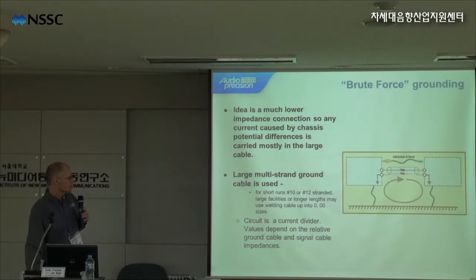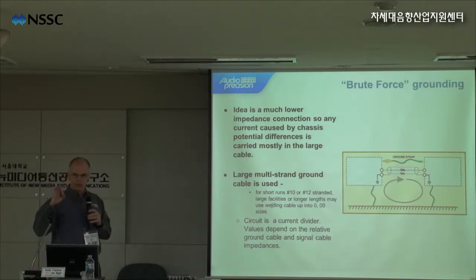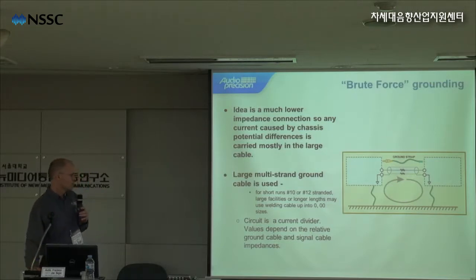So it's a multi-strand ground cable with, for short runs, it can be number 10 or number 12 stranded. And for large facilities or longer lengths, they can use something even like a welding cable, which is a very large diameter conductor. This is called 0 or double 0, so it's a really large conductor. The circuit is a current divider, and the values depend on the relative ground cable and signal cable impedances.